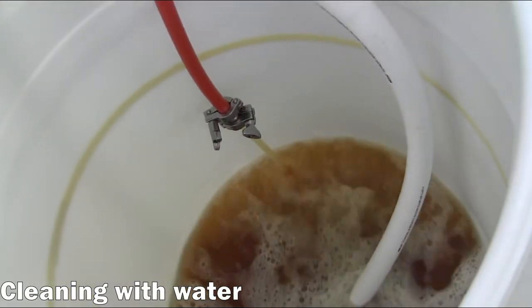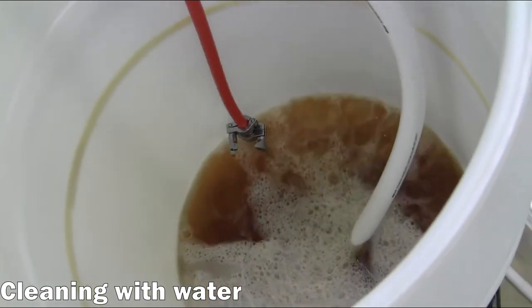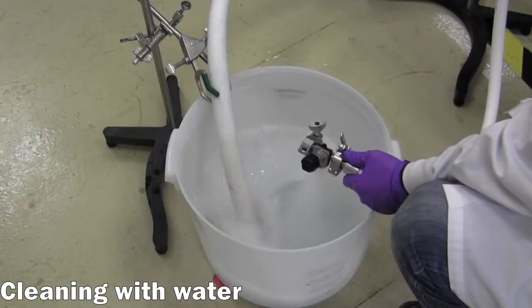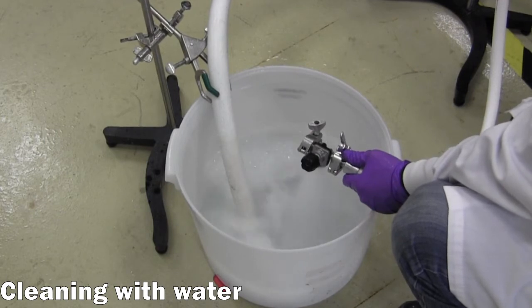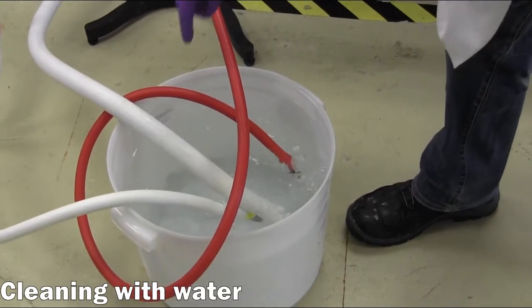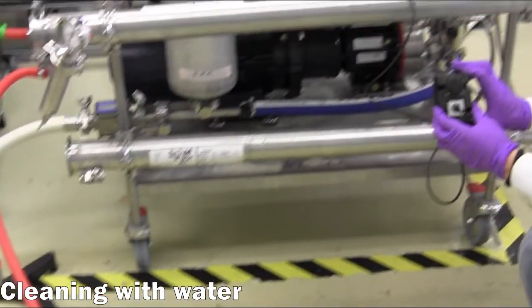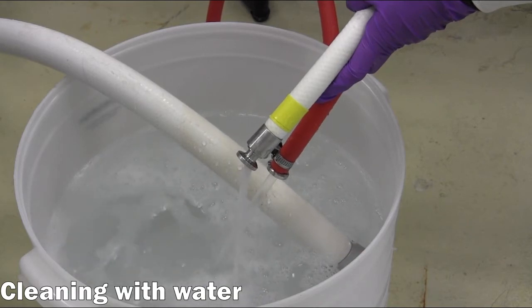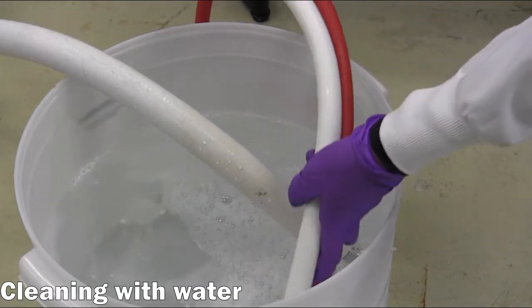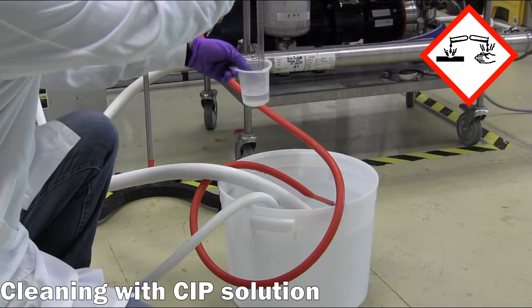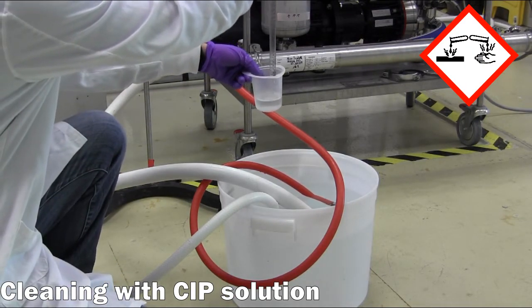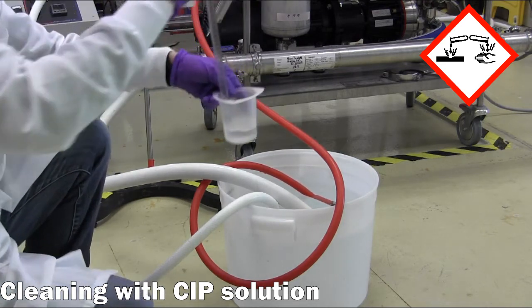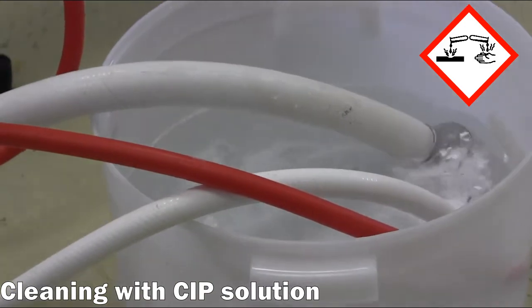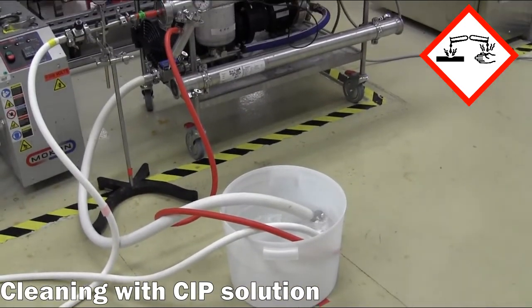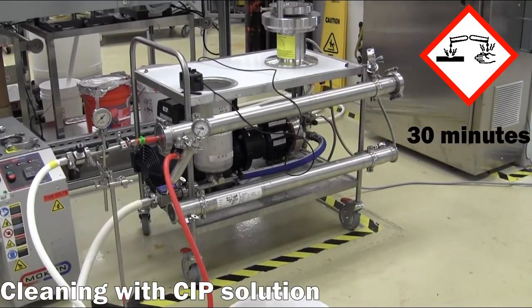Post-experiment cleaning. After the material has been fully processed to desired specifications, the system will need a thorough cleaning, beginning with a water flush. Fresh water is supplied to a bucket where the feed, retentate, and permeate hoses are placed. Then the pump is started so the water is allowed to recirculate with periodic flushes to the drain while replacing with fresh water. Next, CIP100 is introduced to create a caustic cleaning solution that will better clear material from membrane pores and surfaces. Again, all hoses are placed in the CIP solution bucket and the solution is recirculated for 30 minutes.